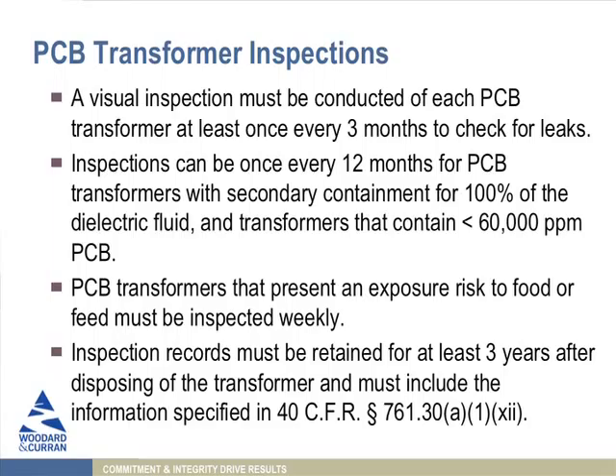If you have a PCB transformer - 500 parts per million or more - you have to inspect it every 3 months to check for leaks. There's one exception: you can do it once a year as long as the transformer has secondary containment and contains less than 60,000 parts per million PCBs. You want to keep these inspection records for at least 3 years.